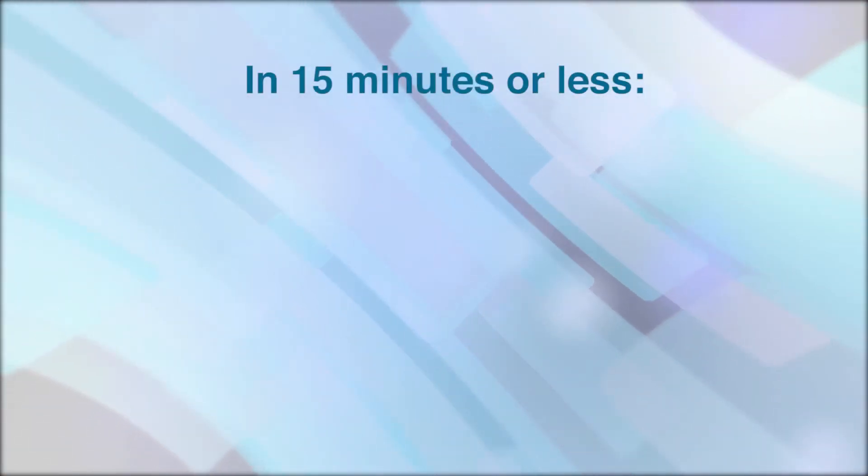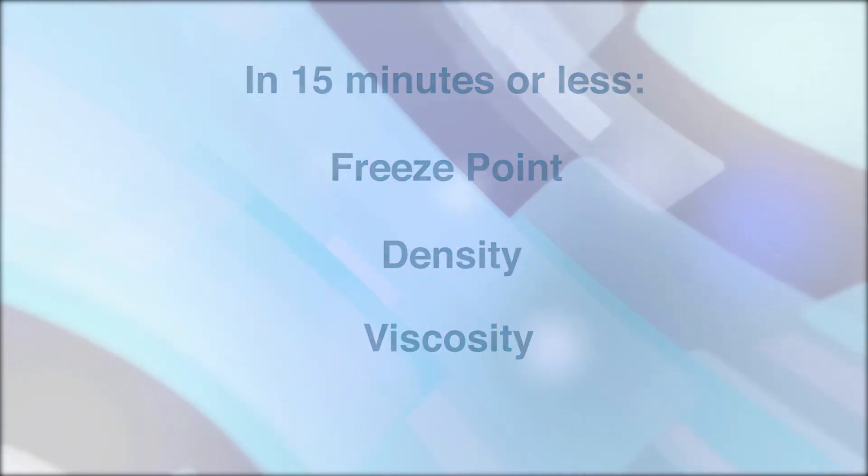You can run three critical tests in less than 15 minutes in a single instrument: freeze point, density and viscosity at both minus 20 degrees Celsius and minus 40 degrees Celsius.